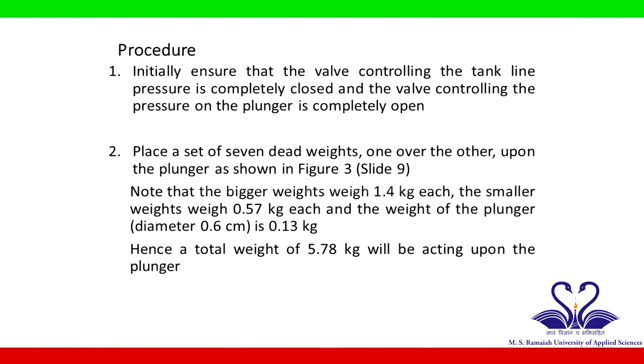The initial reading on the pressure gauge should be 0 kg per centimeter square. For this, the tank line valve should be completely closed and the plunger valve should be completely open. A set of 7 dead weights are then placed one over the other upon the plunger.